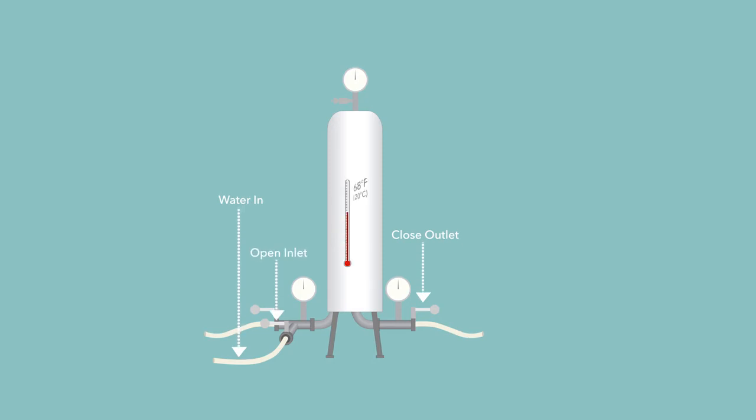Rinse with ambient water, 68 degrees Fahrenheit or 20 degrees Celsius, at 1.5 to 2 times the speed of your filtration. Over 5 minutes, increase water temperature to 140 degrees Fahrenheit or 60 degrees Celsius.